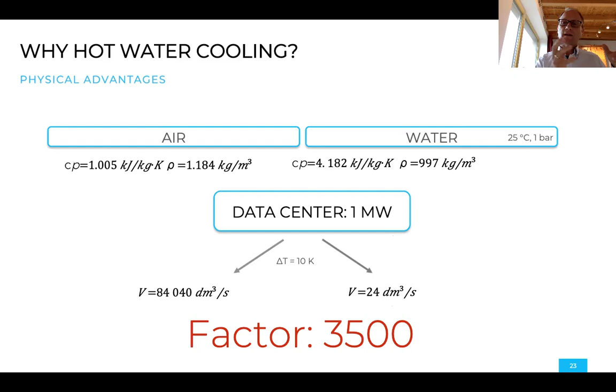Tesla, for example, cools everything with water because it's more efficient than air. As a comparison, for a 1 megawatt data center cooled by air, you need about 84,000 liters per second of air. If you use water instead, you only need 24 liters per second—a factor of about 3,500 between air and water. So it makes total sense to look closer at water, despite people's fears about mixing water and electricity, which is something we've addressed.